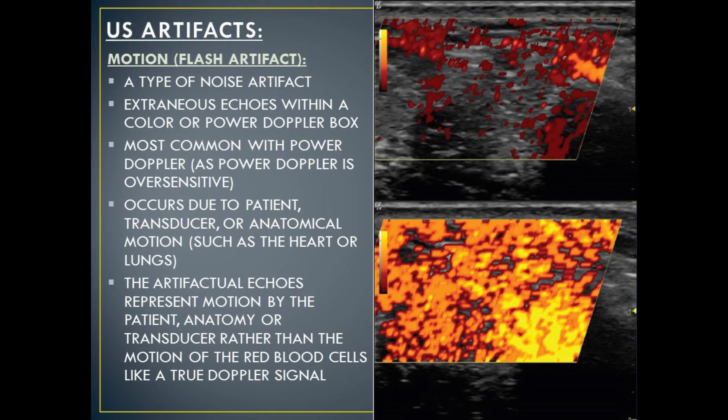The next type of ultrasound Doppler artifact is known as motion or flash artifact. This is a type of noise artifact — extraneous echoes within a color or power Doppler box. This is most commonly seen with power Doppler, as power Doppler is oversensitive. This occurs due to the patient, the transducer, or anatomical motion, such as movement of the heart or the lungs. The artifactual echoes represent motion by the patient, by anatomy, or by the transducer, rather than the motion of the red blood cells, which is a true Doppler signal.